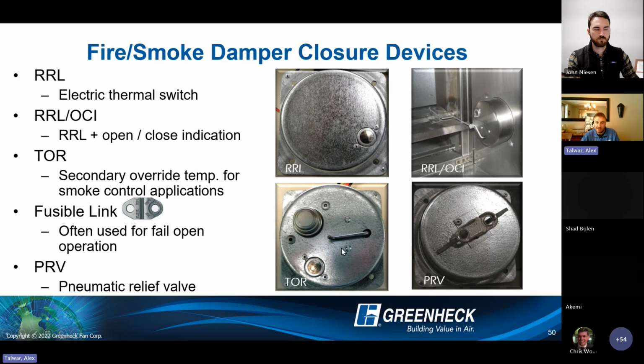TOR is a closure device on the bottom left there. That's essentially a temperature override device. So you'll probably see these most often in a smoke control application. It's got a low limit thermostat, might sense an increase in heat, close the damper, but now you have the ability to override the low limit thermostat, bring the high limit thermostat into play, and reopen the damper until that temperature is reached. Then you're probably more worried about containment than active smoke exhaust, and then you just want to close the damper and prevent the spread of flames. So that's the TOR device, temperature override.